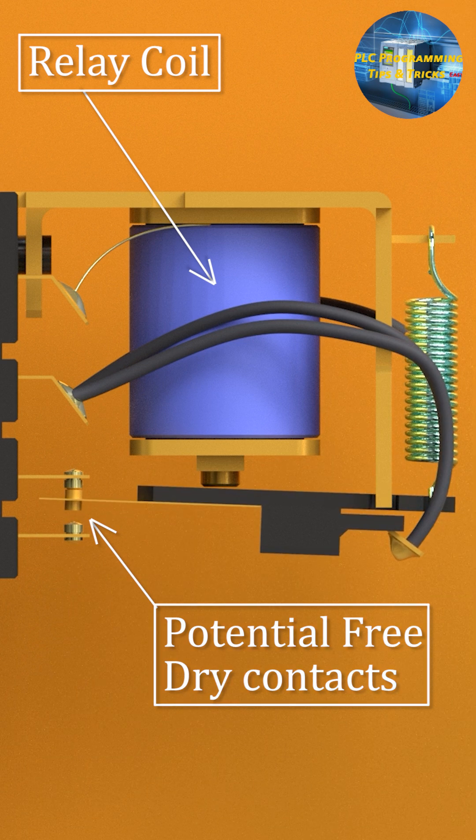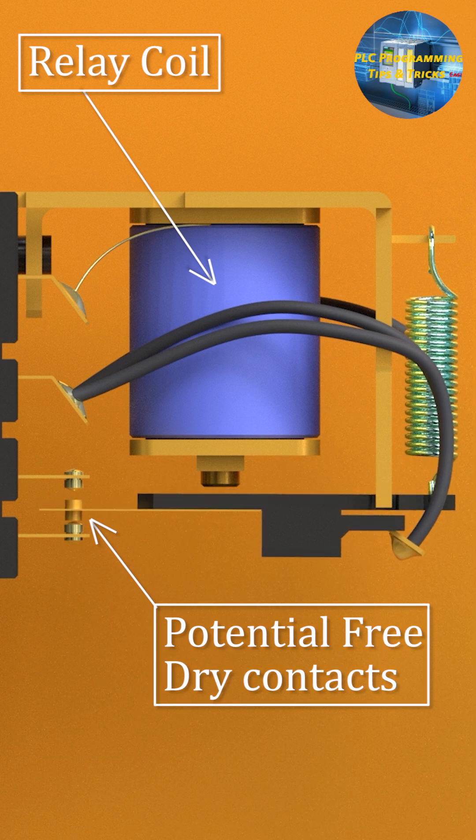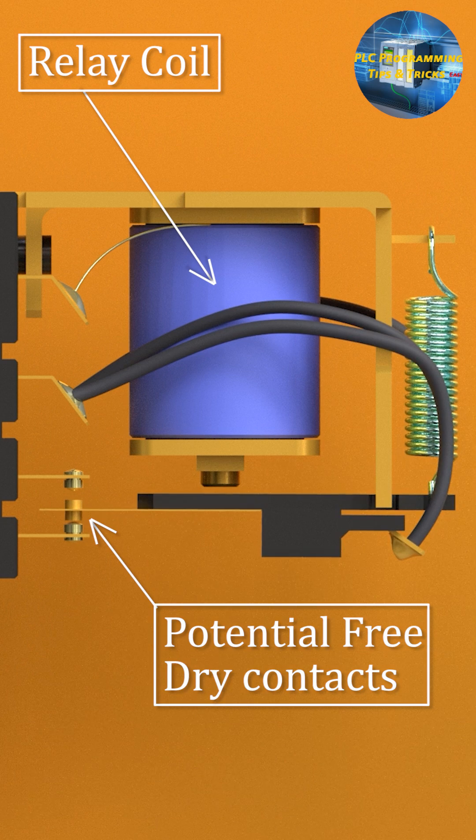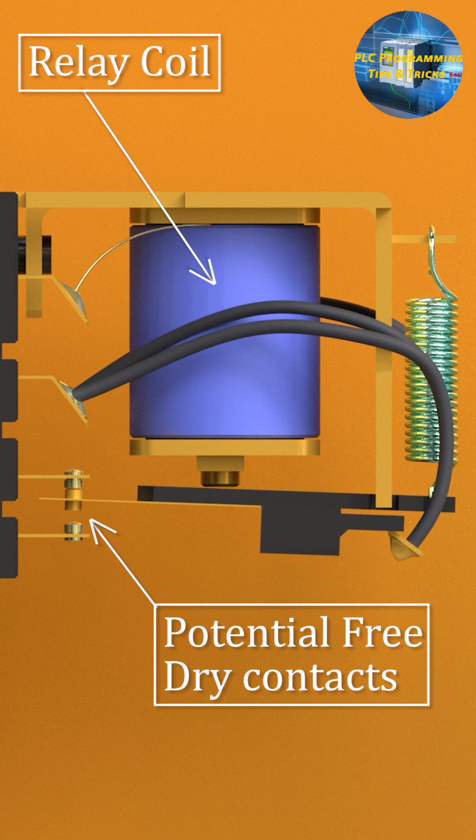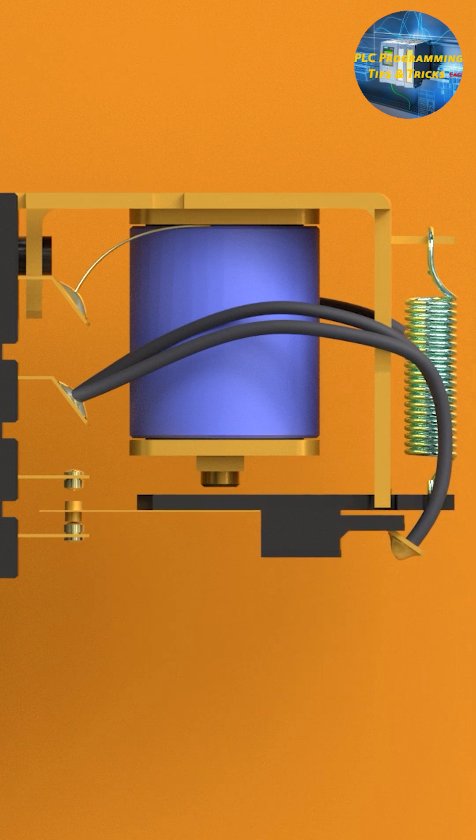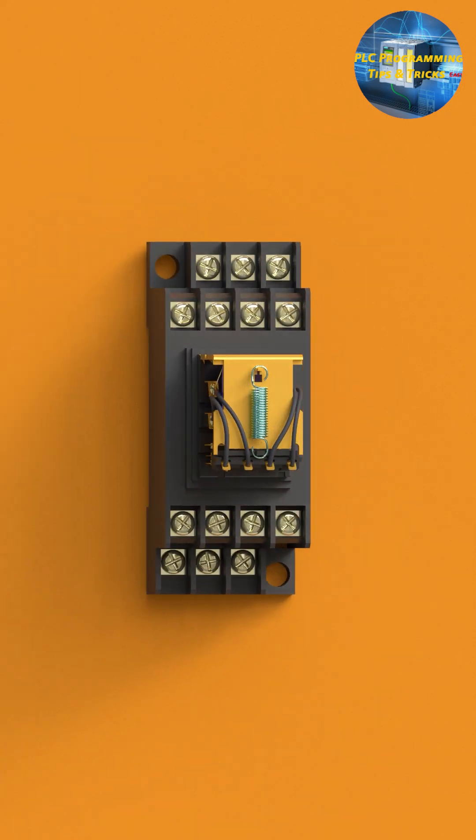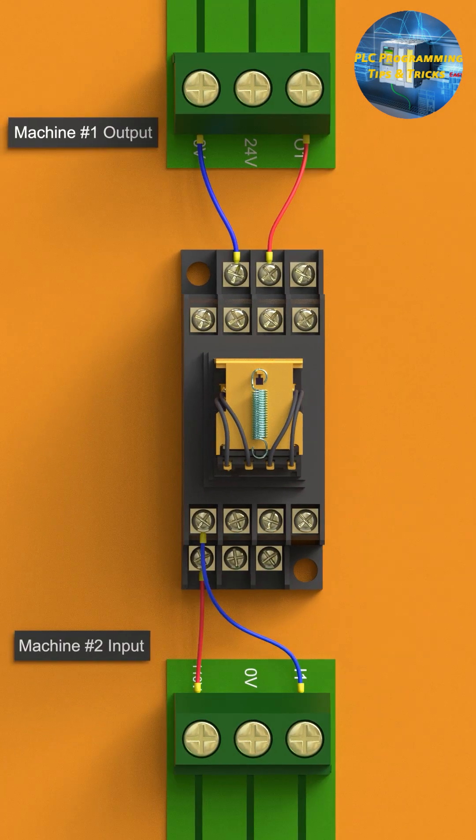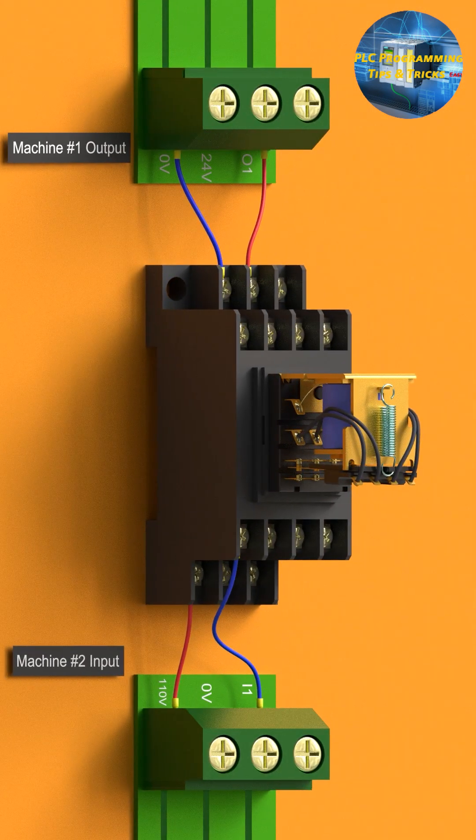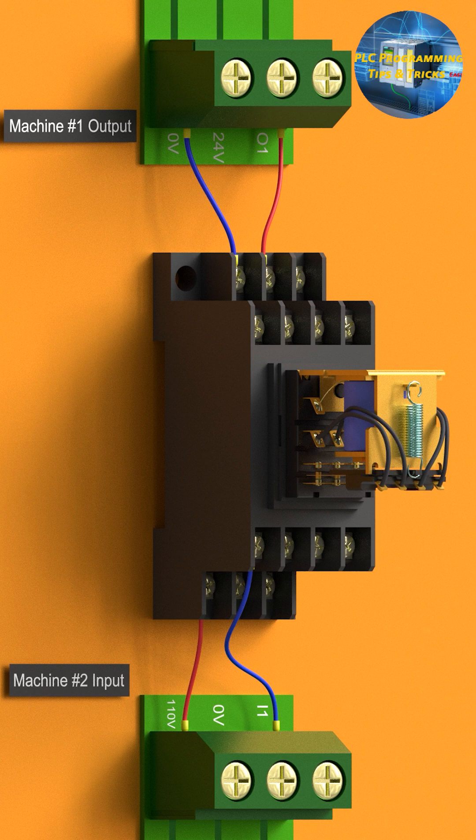The relay coil controls a contact's open or closed state, but the voltage you pass through the contact comes from your own external source, not from the relay. This makes dry contact safe and flexible. You can use them to switch AC or DC signals without interference from the relay's internal power.